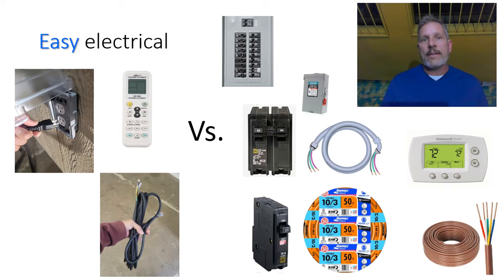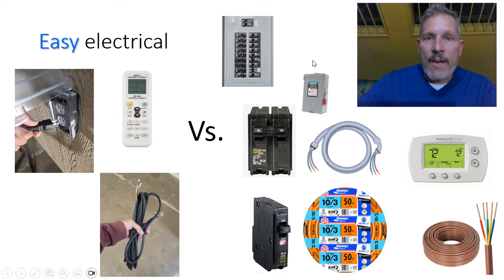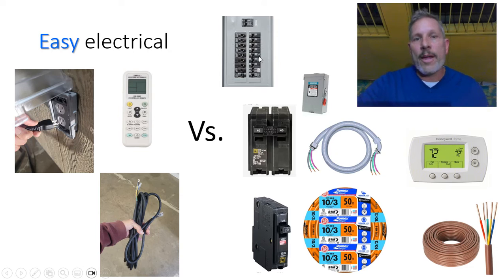So from the top, first thing, mini splits have a much easier electrical system for installation than a traditional split system, be it either a heat pump or air conditioner. Why? Well, the first thing, you have a breaker panel here that needs a 240 two-pole breaker, running Romex to this disconnect box, and then from the disconnect box, the whip to the outdoor unit, and then Romex from the indoor unit to a single pole breaker back to the breaker panel, and then thermostat wire from the thermostat to the indoor unit, and thermostat wire connecting the indoor unit and outdoor unit. A lot of work.